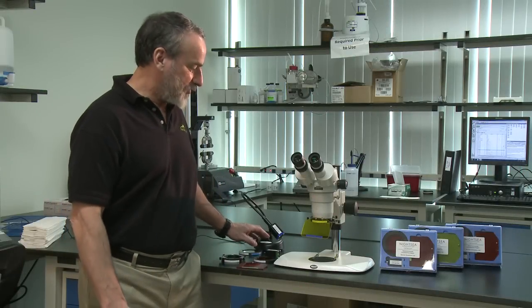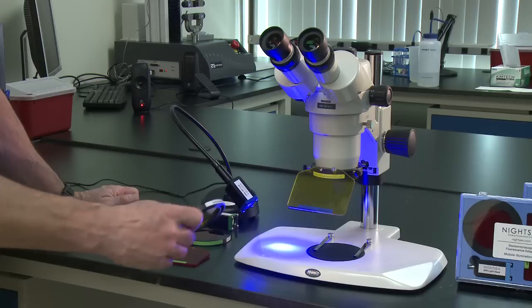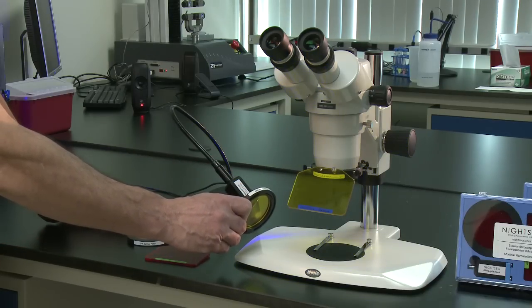There are just two elements required for fluorescence: a light source that will excite the fluorescent material, and a barrier filter that will block the reflected excitation light and transmit only the fluorescence. The NightSea Stereo Microscope Fluorescence Adapter is a complete modular solution that provides excitation light and a simple means of inserting the barrier filter in the emitted light path.